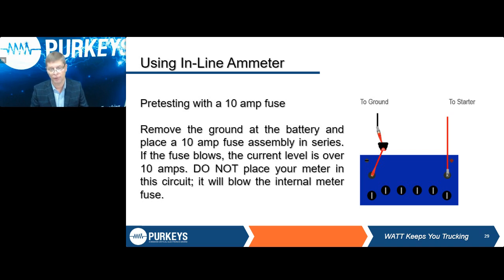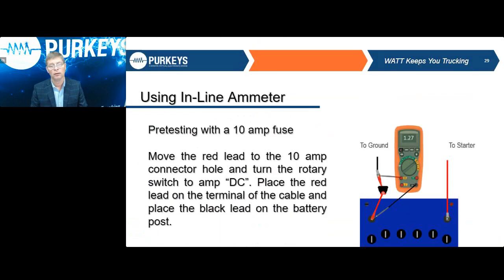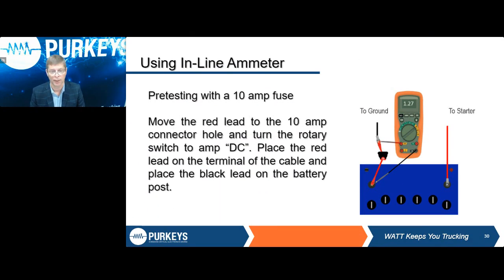So with your fuse holder in line, take your meter, again, set it up to amps, move your red lead over to the correct position, and you want to put it in parallel to that fuse holder. All you're trying to do is make sure we're not making and breaking that circuit.